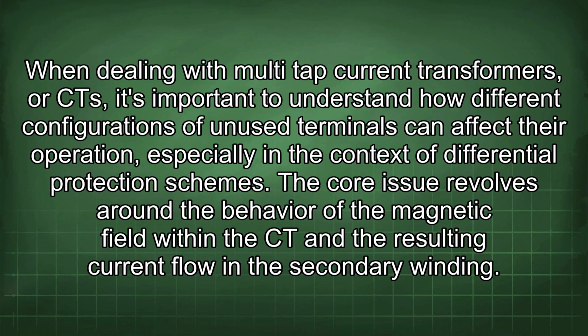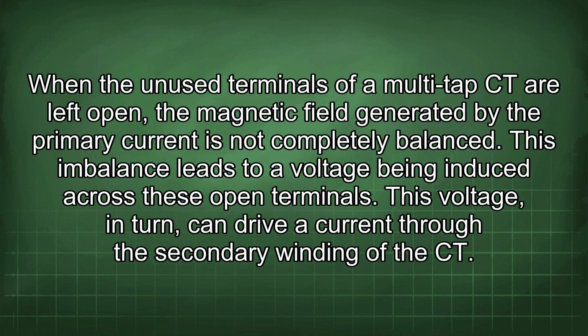When dealing with multi-tap current transformers, or CTs, it's important to understand how different configurations of unused terminals can affect their operation, especially in the context of differential protection schemes. The core issue revolves around the behavior of the magnetic field within the CT and the resulting current flow in the secondary winding. When the unused terminals of a multi-tap CT are left open, the magnetic field generated by the primary current is not completely balanced. This imbalance leads to a voltage being induced across these open terminals.